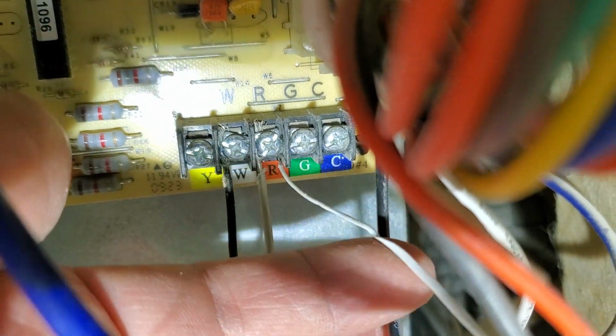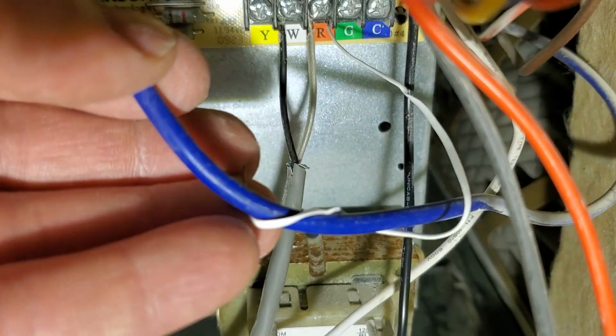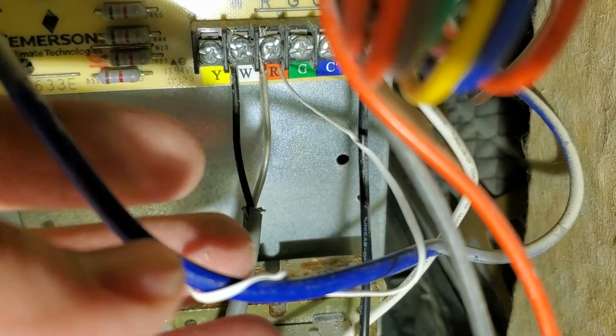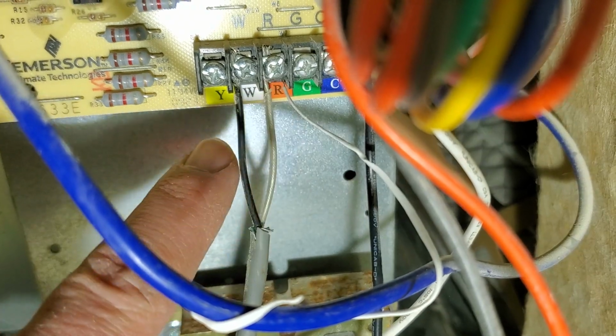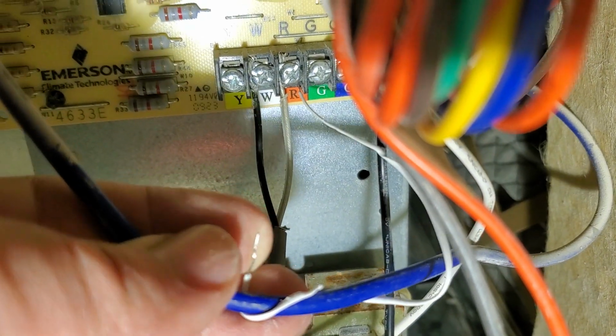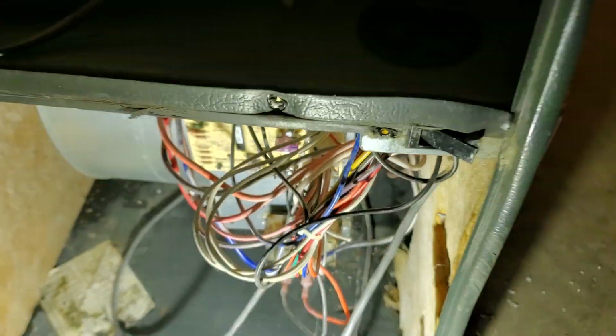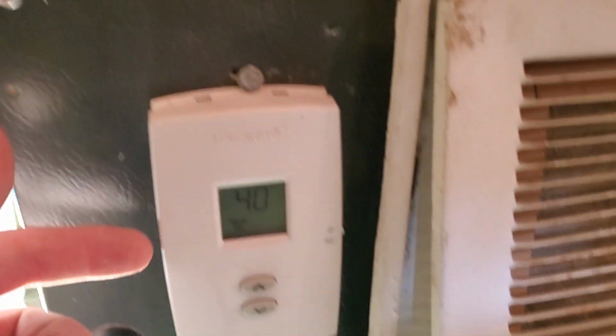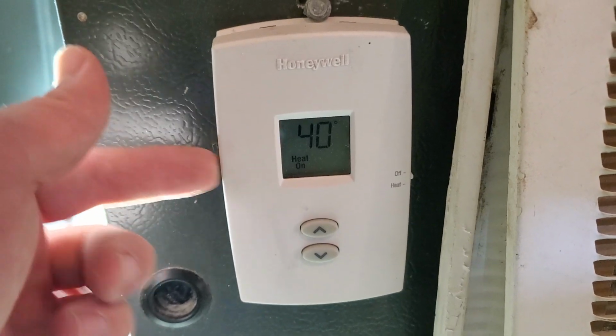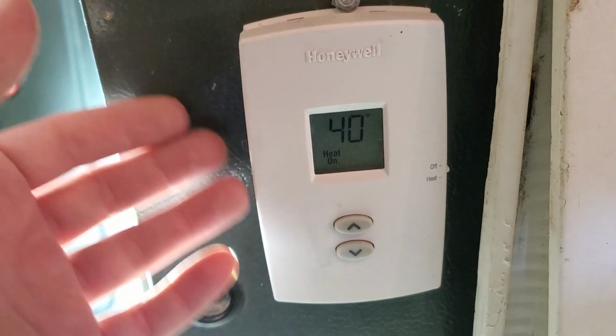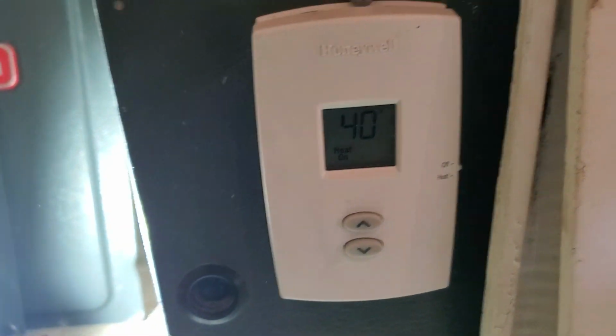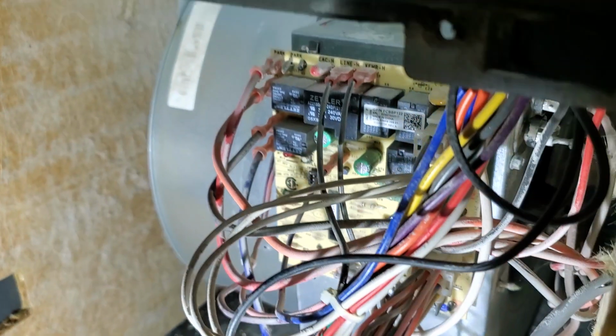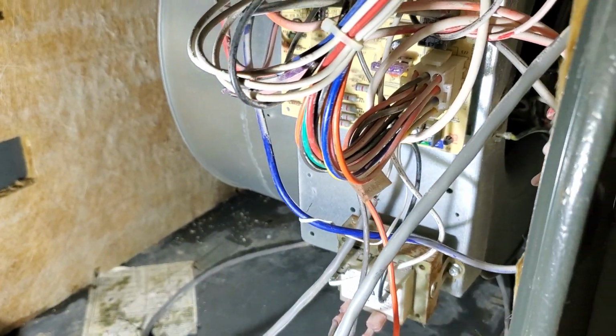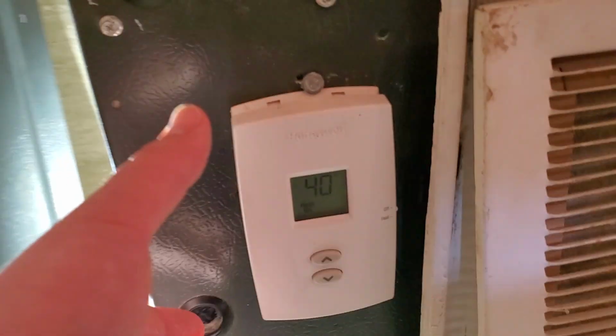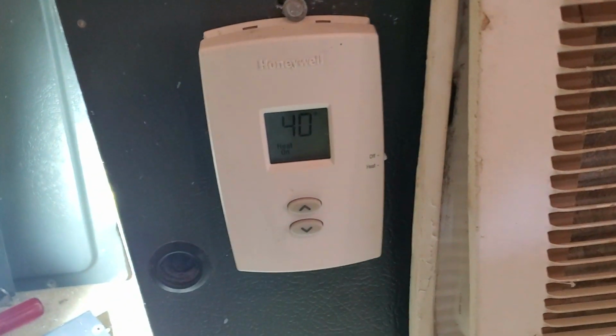You see this other wire right here? That's actually just a twisty tie. That is our way of being able to short that out easily. We can just directly cross the R to the W, and then the furnace will run continuous. And sometimes we have to do that because if the room is below 32 degrees, when you first start the furnace, your thermostat, if it's a smart thermostat, will not turn on because it's protecting the furnace because it thinks that the furnace froze, which isn't necessarily the case. So that's why we have that little jumper wire there on the ready in case we do need it. But just the R and the W, and then those come over to the thermostat. I'll pull it off here really quick and show you what it looks like.